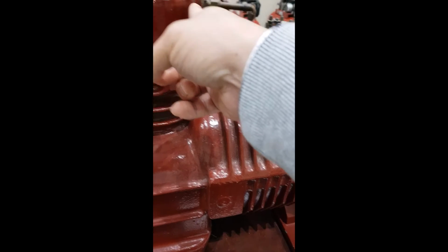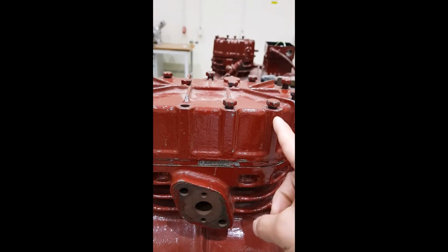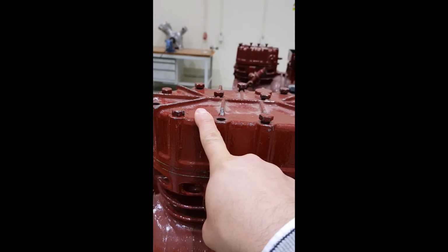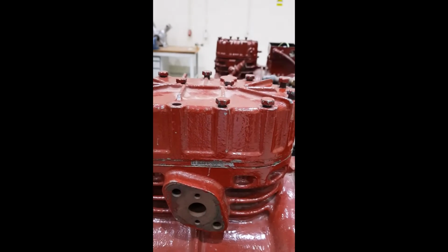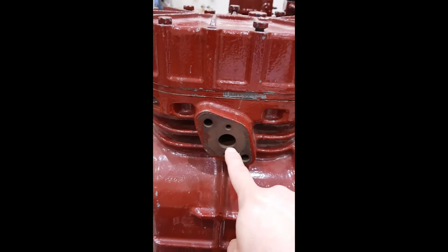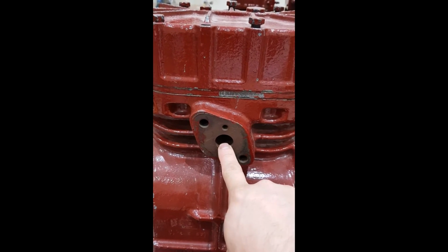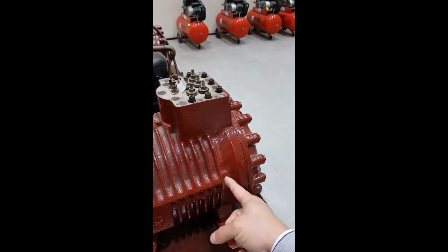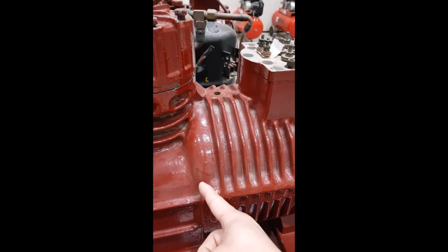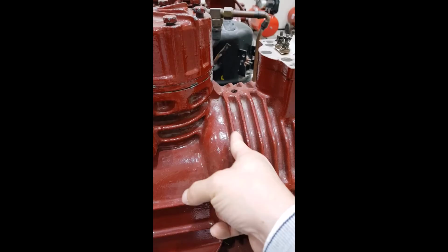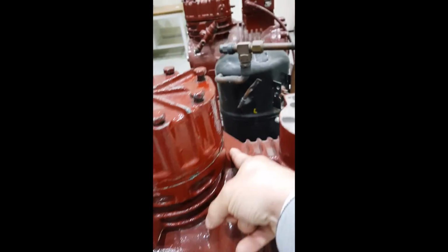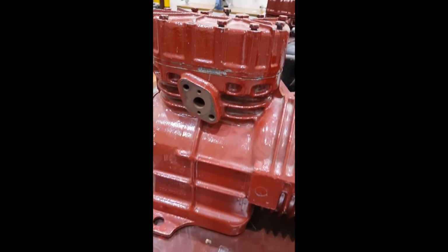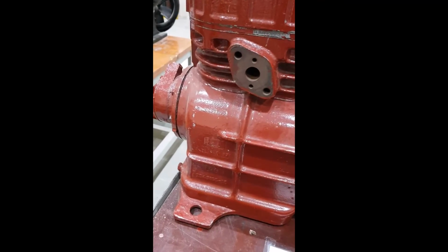From there, it joins the compressors. We have two pistons over here for compression, and the air is discharged this way. The reason the air comes from inside is to apply some cooling, just like we watched in the video. So it applies some cooling, and from there it enters the cylinder head and cylinder block for the gas to be compressed.